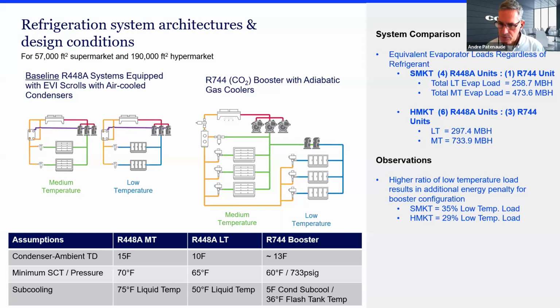And what happens there is because your supermarket has higher low temp percentage of total load, that means that when you look at your CO2 system, your medium temp compressors have to do more boosting. They've got an extra 6% more capacity to boost up. And I'll come back to that because it has an impact on efficiency when you compare one supermarket to hypermarket. So the other observation we saw is that, of course, CO2 has an efficiency advantage, particularly in low ambient. And so the areas that have more low ambient hours of operation tends to do better.